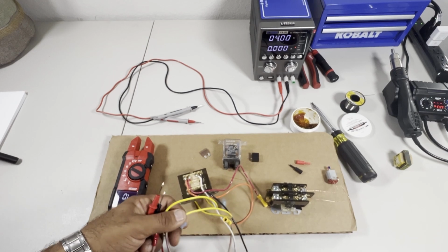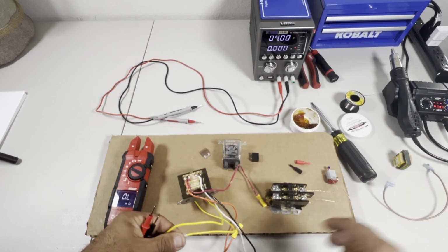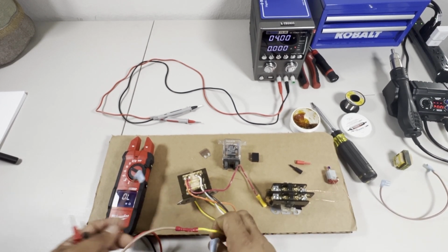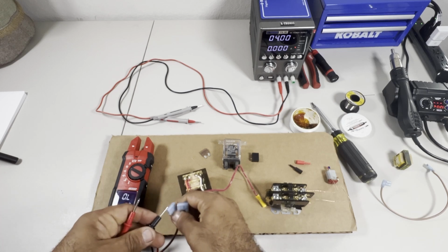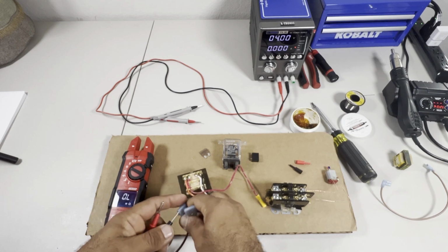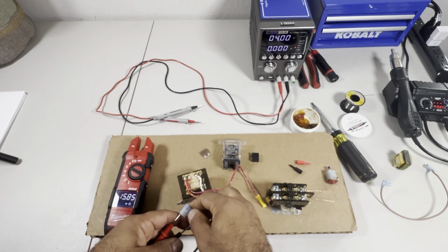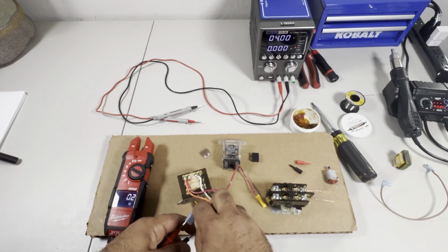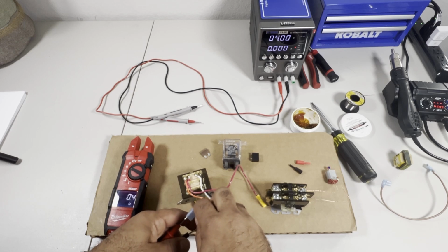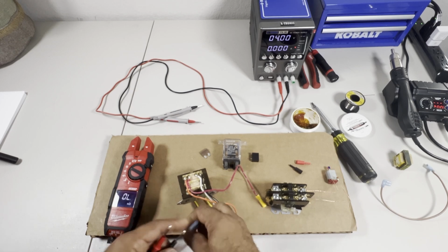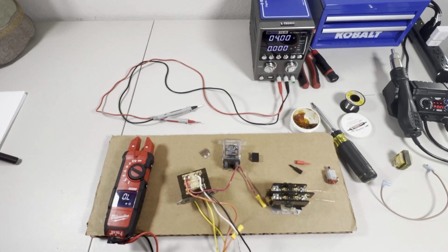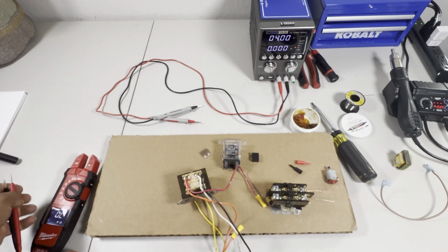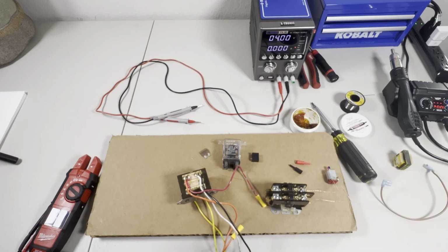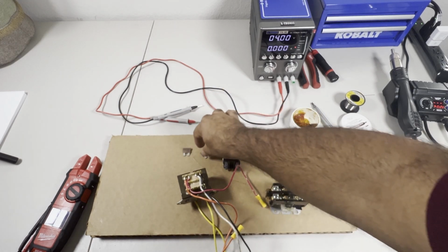Same thing on the output. Again, that's just another loop of the wire, then it goes completely through the transformer. So you want to check the output as well, and when there is no power to the transformer, you should read a very, very low ohm reading. And if you do, most likely your transformer is good. It could still be used.